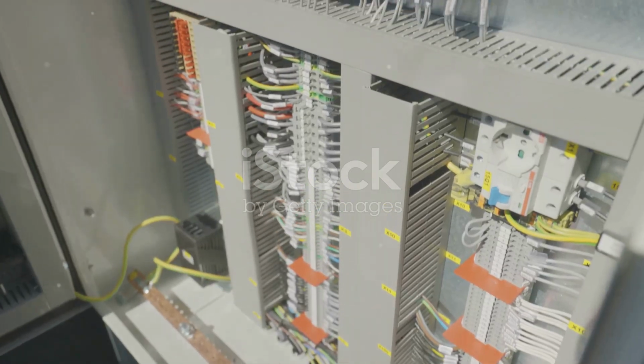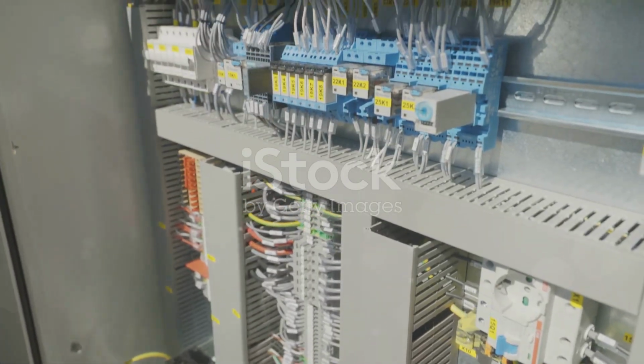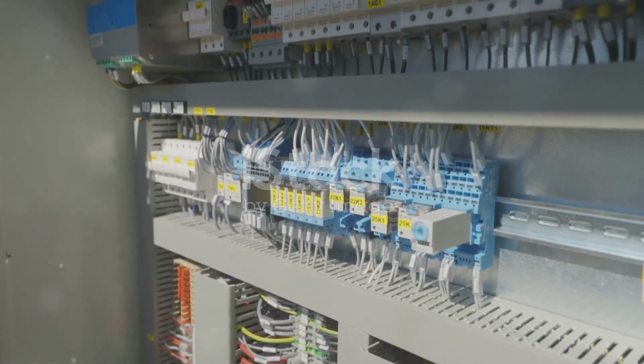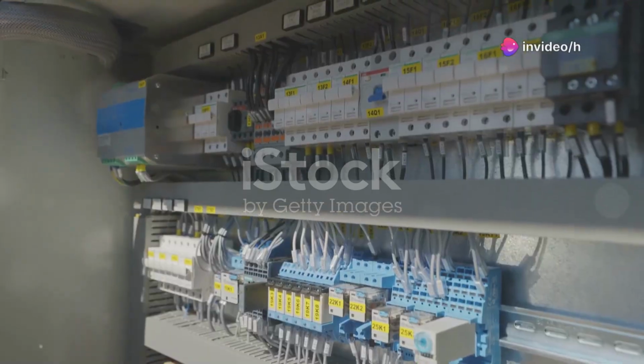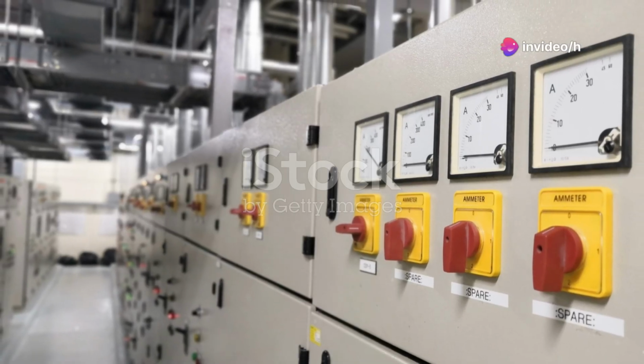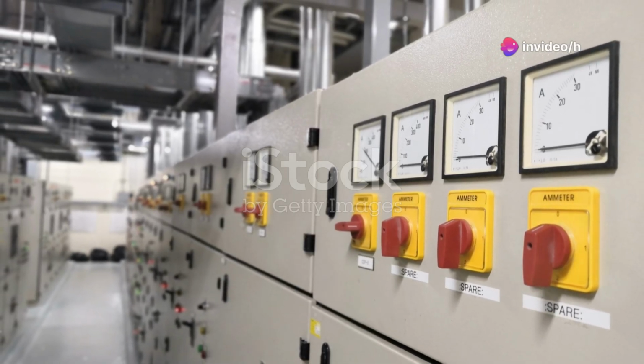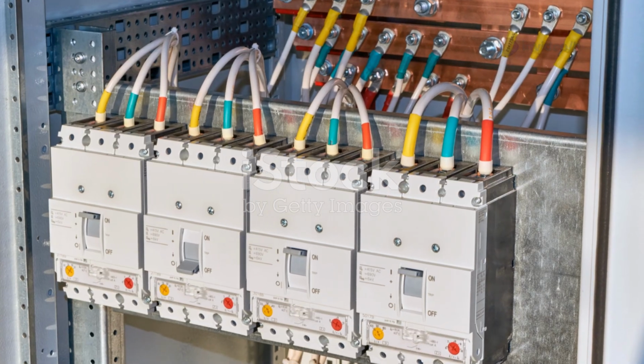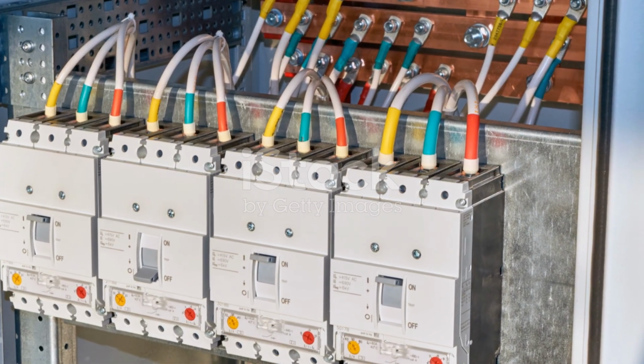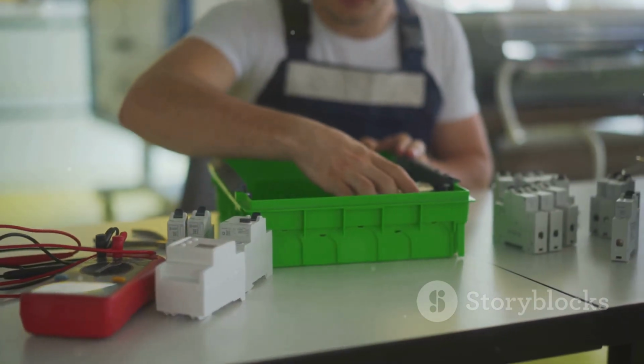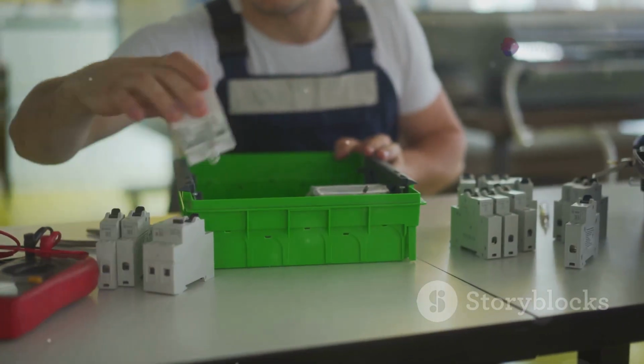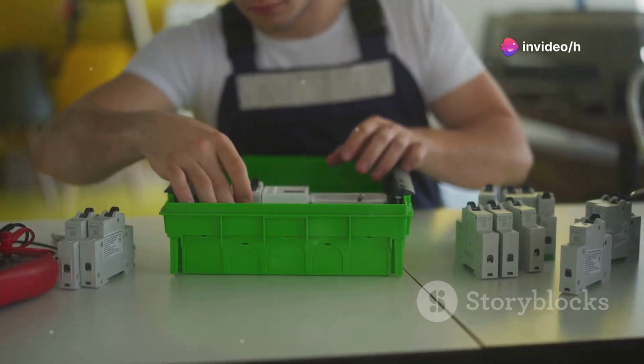For three-phase circuits, always use a 4-pole RCCB, while a 2-pole RCCB is suitable for single-phase circuits. Choosing the right type ensures comprehensive protection for every part of your system, whether you're dealing with heavy machinery or standard equipment. Snap each RCCB and MCB firmly onto the DIN rail. Make sure they're aligned and locked in place, as a loose connection can compromise safety and lead to equipment failure.